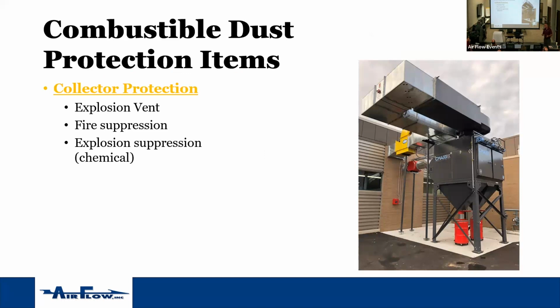You have an explosion vent, which is going to direct the explosion, control the explosion, tell it where to go, dictate how we handle that. Fire suppression is going to stop the fire that's inside of there, because you can have a fire without it exploding. Again, a lot of times fires will happen after the collector's been shut down, after dust going through the collector has stopped, but you still have your pile of dust that's collected in the bottom. A spark may have been sitting in there smoldering, and then that's what starts the fire.